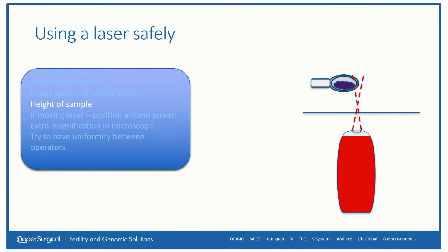If the embryo is raised a bit higher, then the laser beam is no longer focused, and although you'll still get some laser energy hitting the zona, there won't be enough to make the size of hole you're expecting. Instead, you'll end up with a much smaller hole, and then you'll get to thinking there's something wrong with the laser, when actually it's just the position of the embryo in the dish.